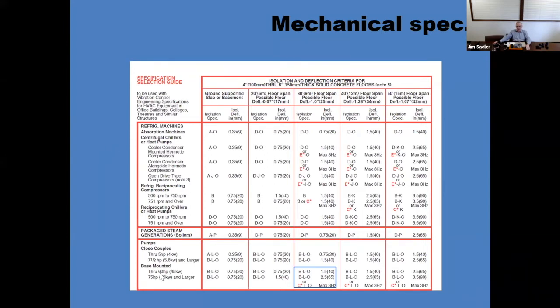We're getting back to the selection of base-mounted pump, and let's say I put it on an upper story with 9 meter structural span. I simply read down, I'll see the letters B, L, and O. Those correspond to the products we recommend. And to the right of that is the recommended static deflection, in this case, 65 millimeters. So that's how much we're going to select the isolators to deflect 65 millimeters.